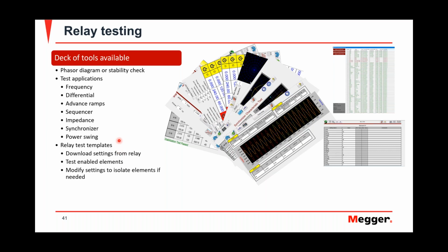If you want to use the relay test templates, you could. Each relay tester manufacturer will have templates that have all those tests included for different relays, and it will only enable the tests that are enabled on that relay. To me, this is more advanced. My advice would always be: understand the tools, understand the protections before you start using the templates available.